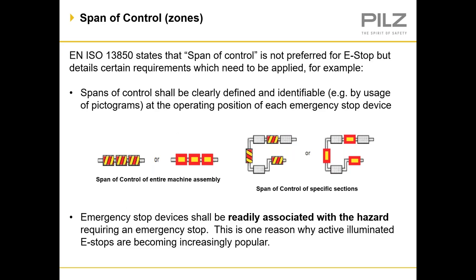EN ISO 13850 states that span of control is not preferred for e-stops but details certain requirements which need to be applied. For example, span of control shall be clearly defined and identifiable by the use of pictograms at the operating position of each emergency stop device. The example on the left shows a pictogram for an entire machine assembly, and the example on the right shows span of controls for specific sections or locations on that machine assembly. Emergency stop devices shall be readily associated with the hazard requiring emergency stop.